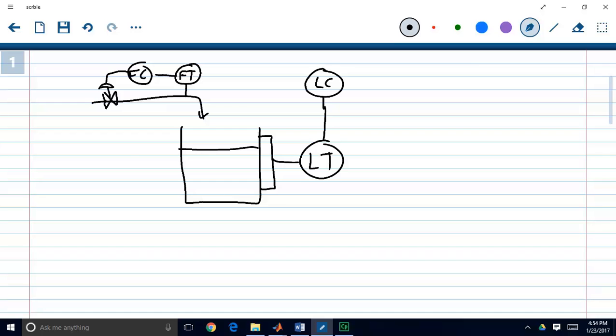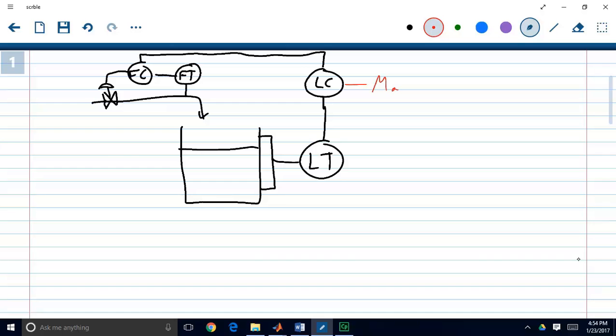The level controller is going to use the inlet flow rate as its manipulated variable. It will try to maintain a certain level determined by the set point we plug in, and it will have a PI algorithm that runs and specifies a particular flow that we want. The level controller will write out its output to the flow controller — essentially giving the flow controller its set point. In this configuration, the level controller is known as the master controller whereas the flow controller is known as the slave controller.